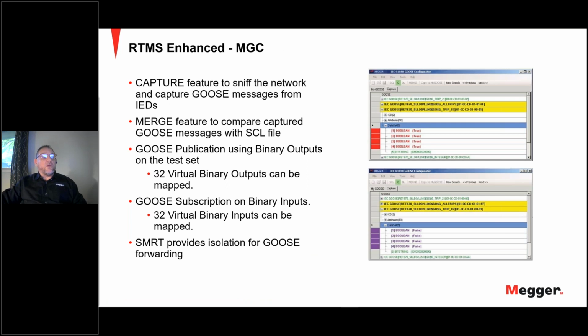Moving on to the Megger GOOSE configurator. The Megger GOOSE configurator software provides mapping of the binary inputs and outputs of the SMRT test set to the desired Goose messages. The Goose messages are read from an available SCL substation configuration language file, or may be automatically detected by scanning the substation network in search of an available published Goose message.